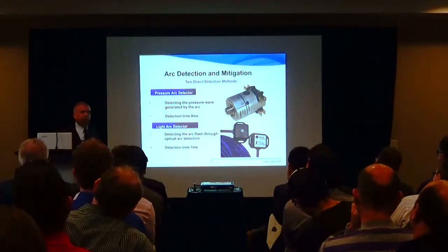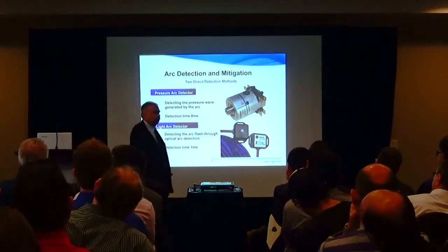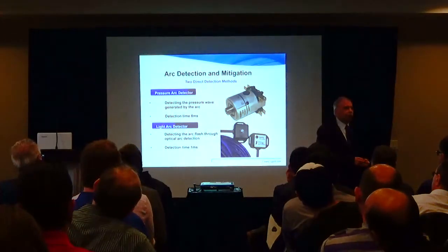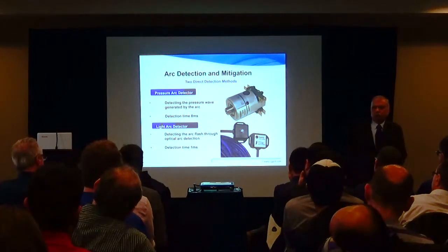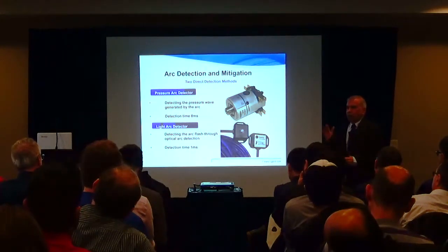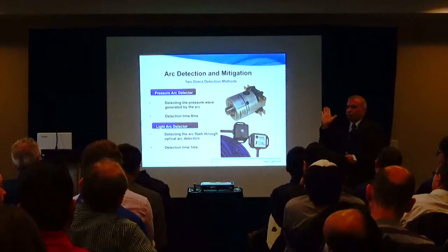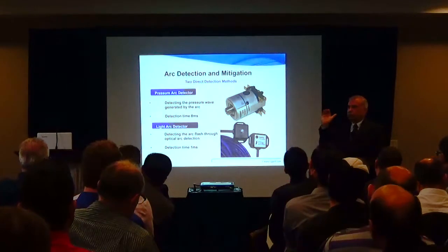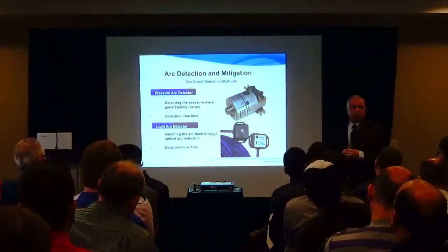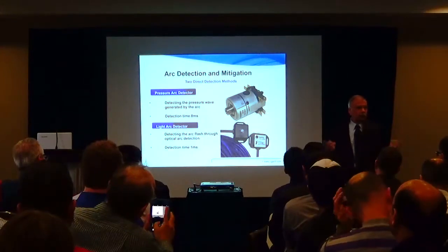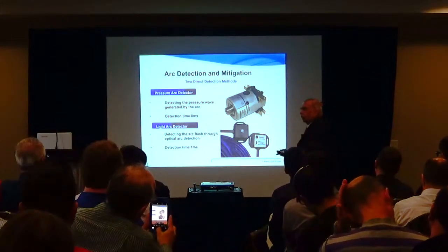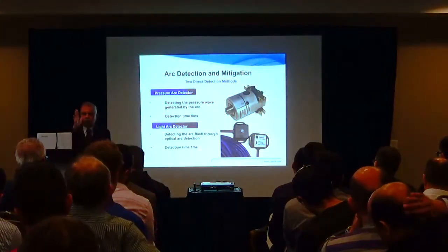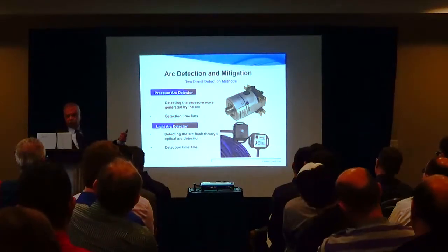So we use these pressure sensors. These pressure sensors came from gas insulated switchgear technology. We've been using them in that kind of switchgear for many, many years. They've been used on SF6 circuit breakers for many years. It's a diaphragm inside. So it's a concave situation. The pressure builds, it becomes convex. So very quickly, it changes the microswitch attached to that diaphragm to give you an indication that your pressure has built inside the equipment. So it adds only 4 milliseconds to 6 milliseconds to the tripping, the action of the diaphragm, and the pressure follow-up.